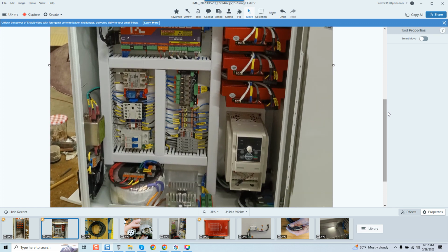The only thing that I wouldn't be fond of, and I've discussed this with the potential client, is the VFD being installed near the drives in the controller. A VFD, in best practice, should never be installed within your electronics enclosure because all of the EMI is trapped. Now, that being said, in all fairness, we do have an EMI filter right here. Again, radiated EMI, you're still really pushing the barrier, and I see no point to it if you were to mount this externally. That's, again, my own personal feeling.